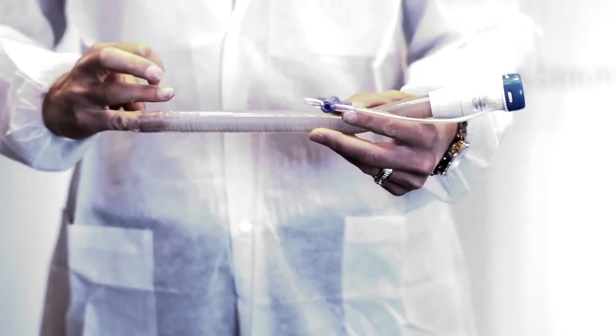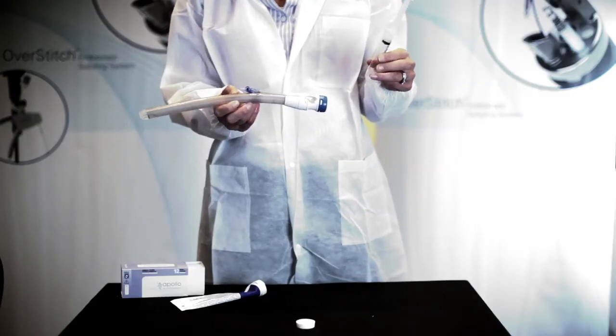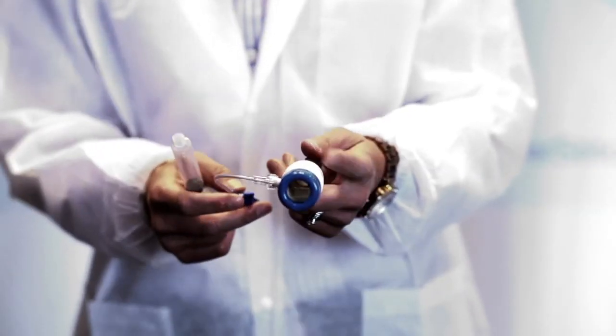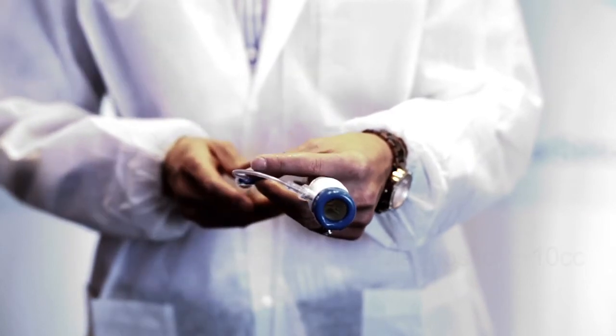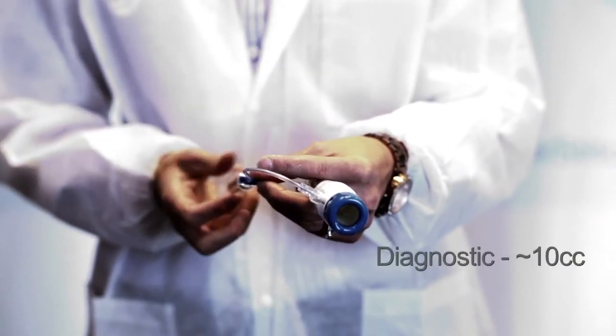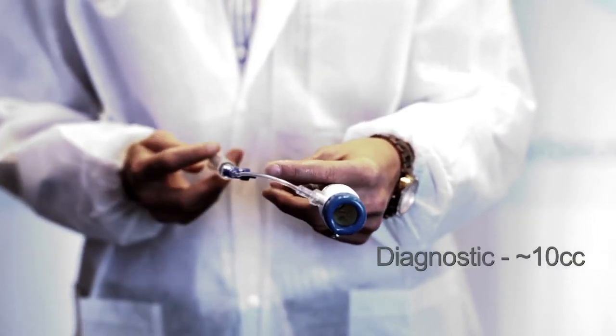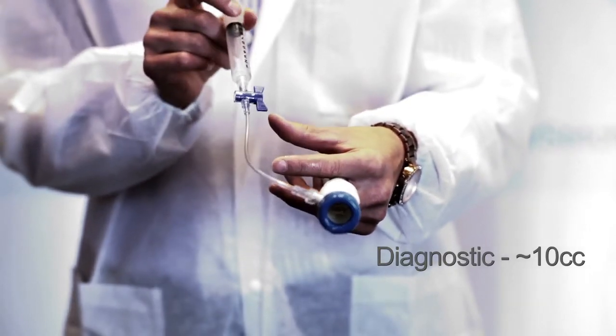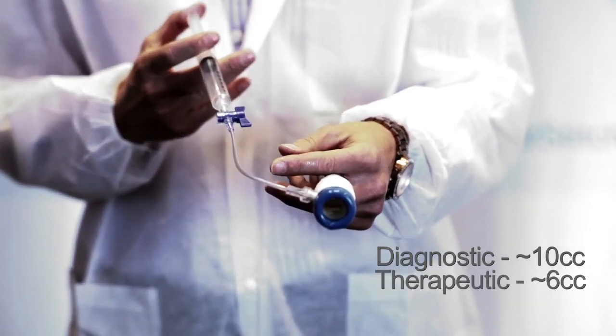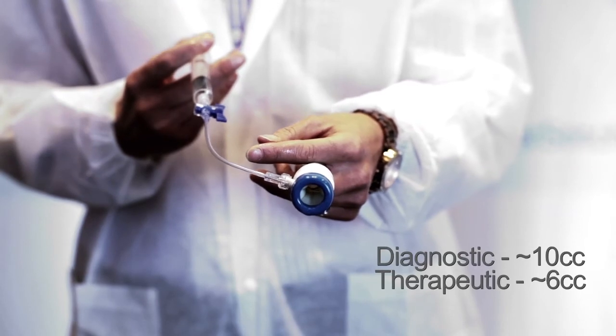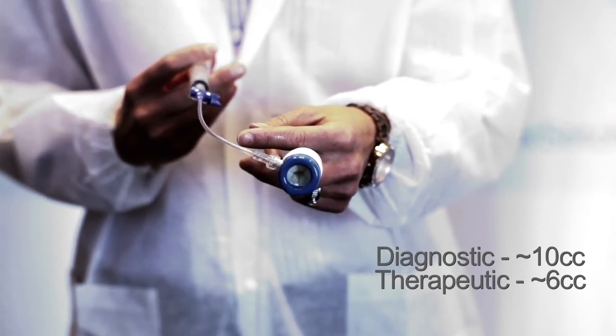The cuff is inflated by attaching a 10 cc syringe and air is injected. Note, for an EGD scope, inflate up to 10 cc's of air, and for a dual-channel scope, inflate up to 6 cc's of air. When inserting the Overtube, it must be placed over a diagnostic EGD scope or a dual-channel scope.